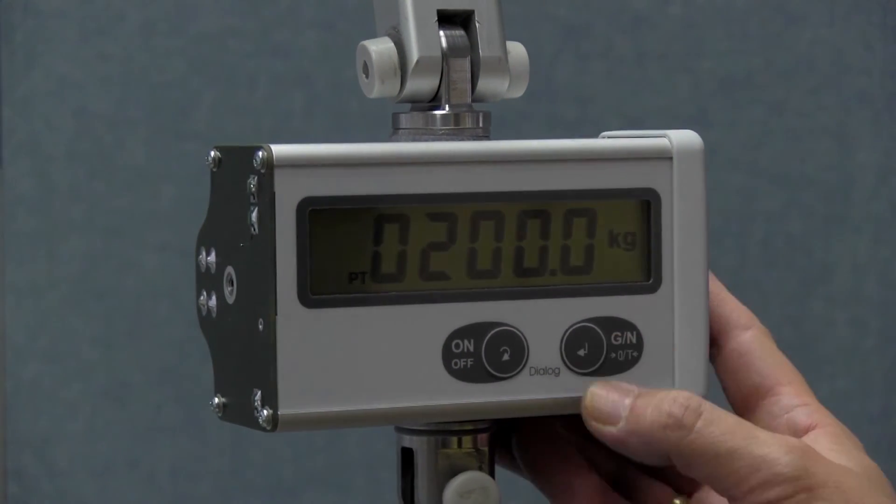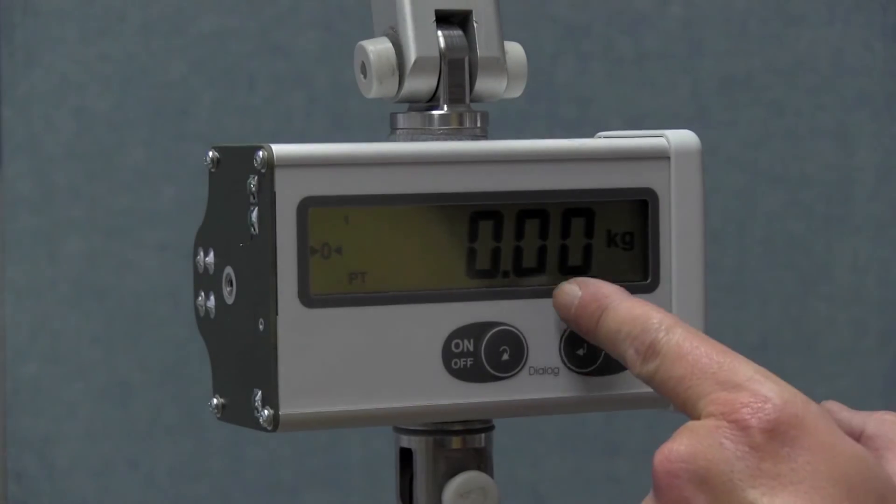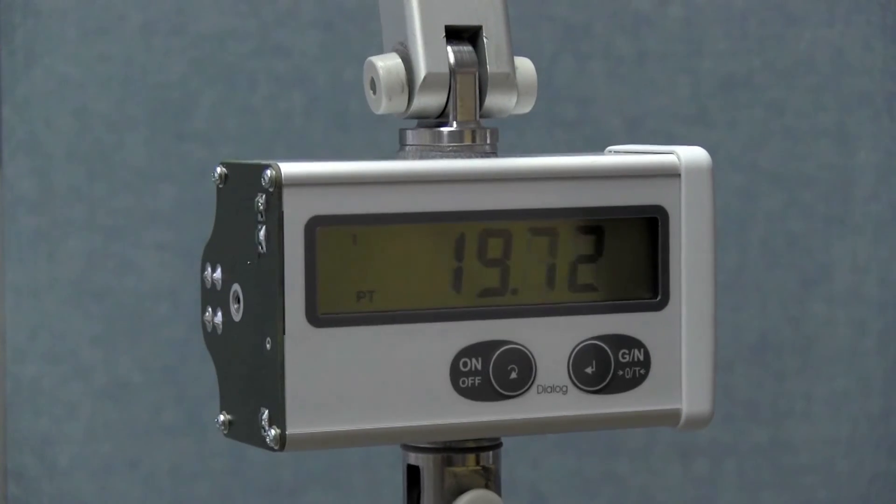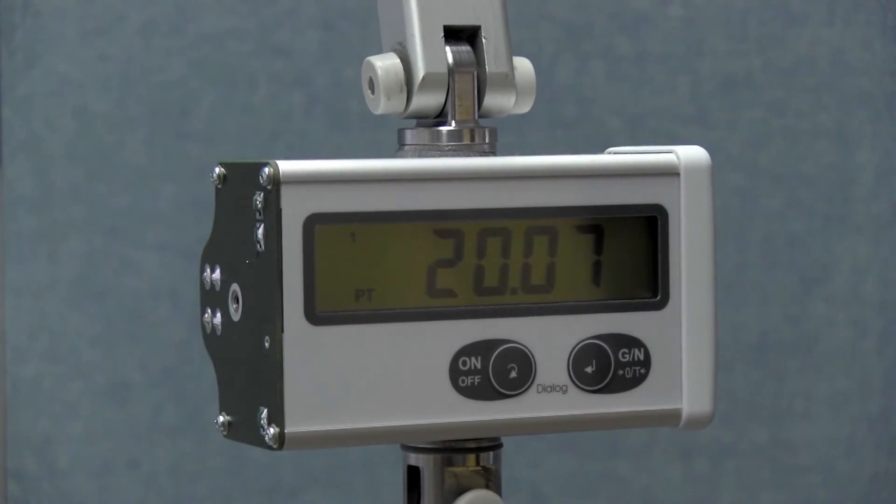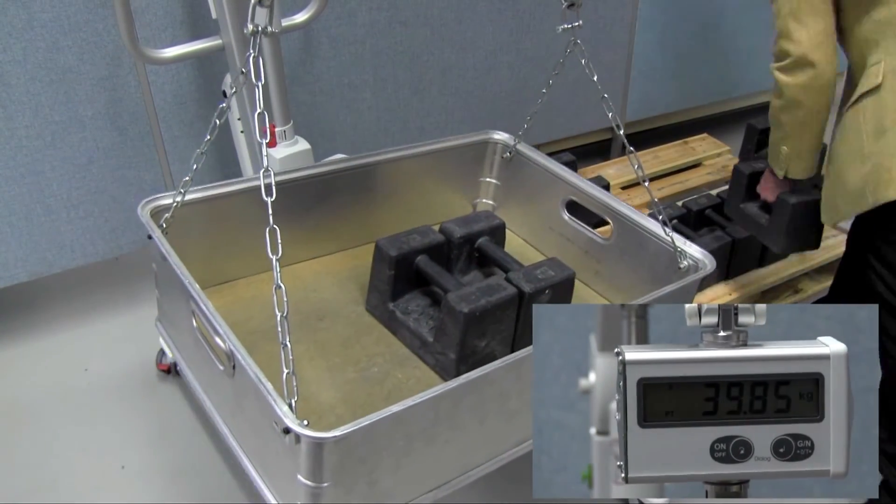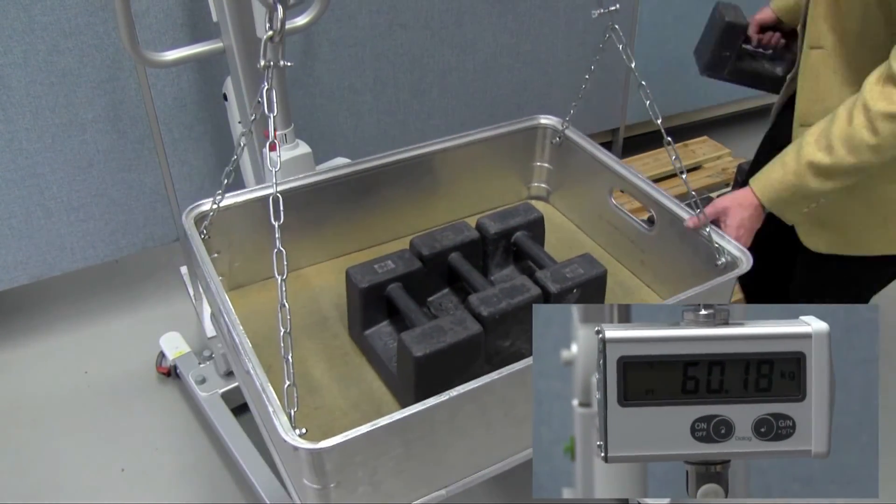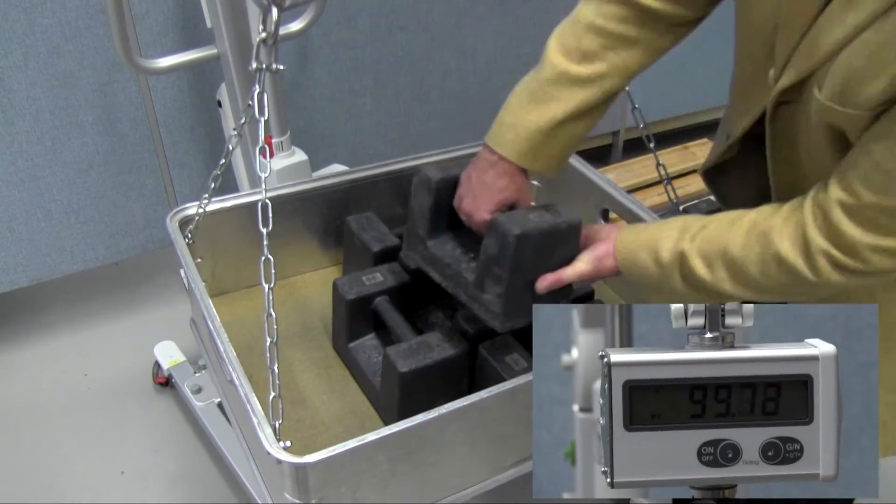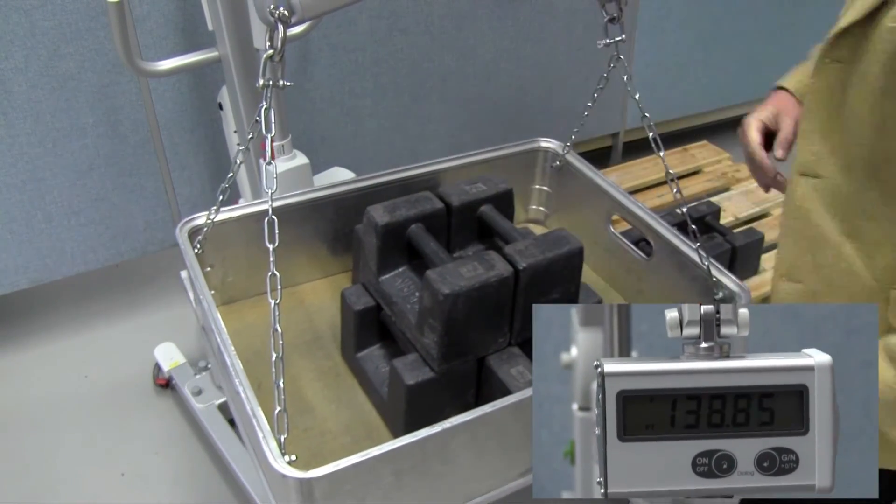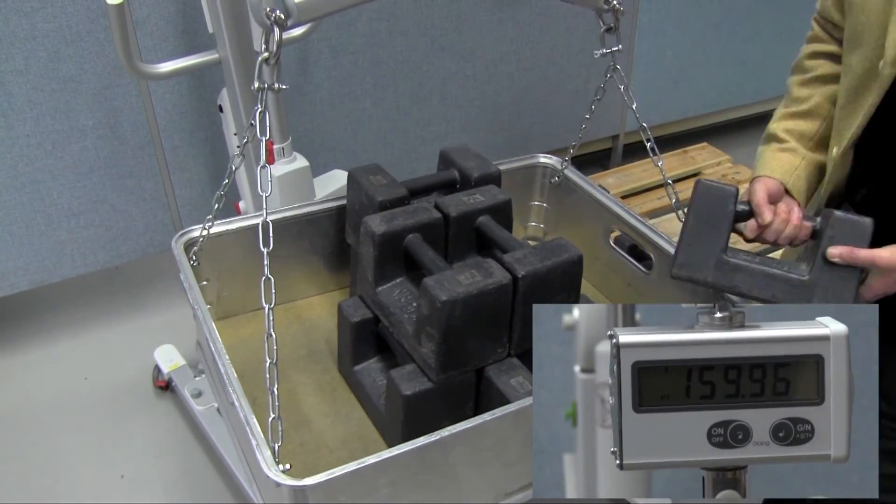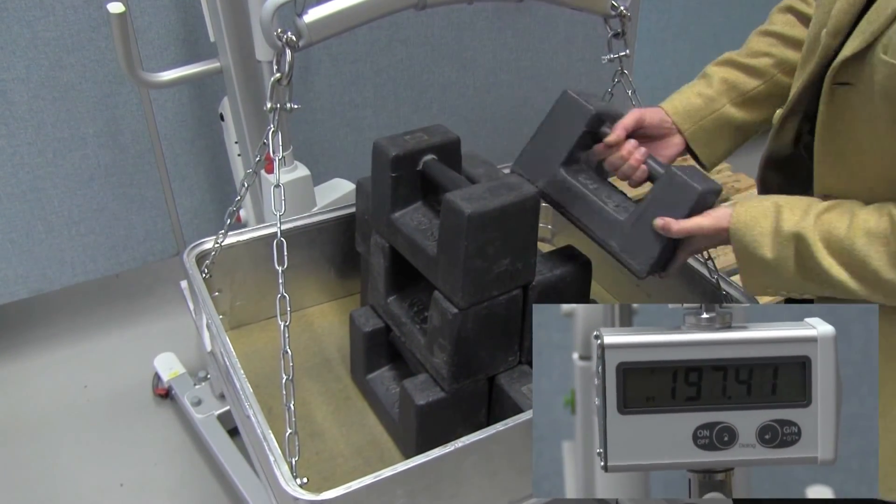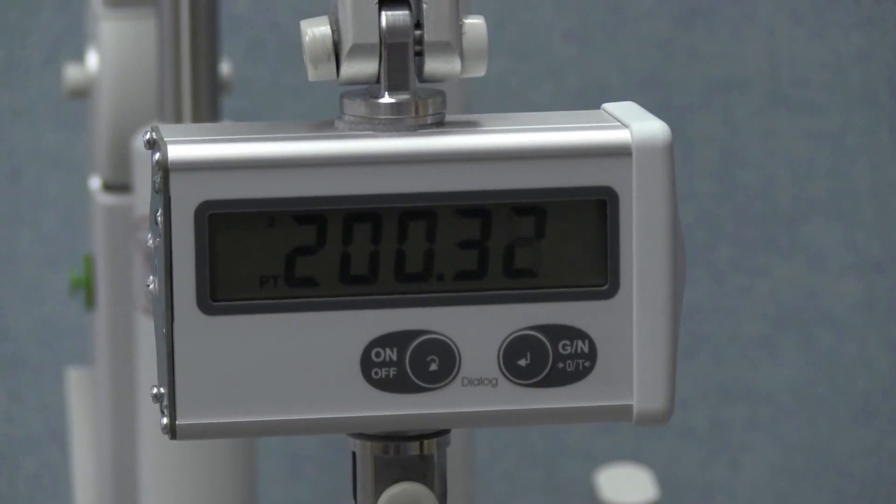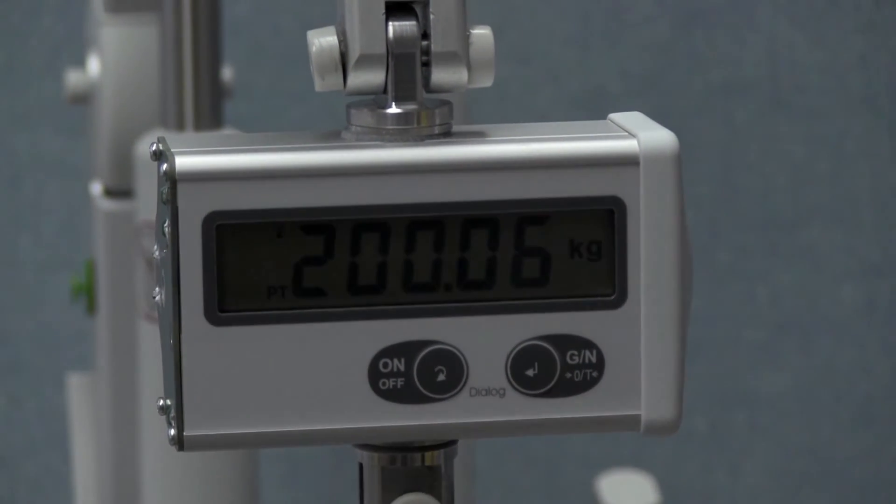When I confirm the test weight of 200 kilograms, the scale automatically assumes its zero value, and I can then add weights to move the test weight up to 200 kilograms. After the last weight is placed in the box, I'm going to press the button on the bottom of the box. 200 kilograms appears in the scale display. I confirm and end the process with the GN key.